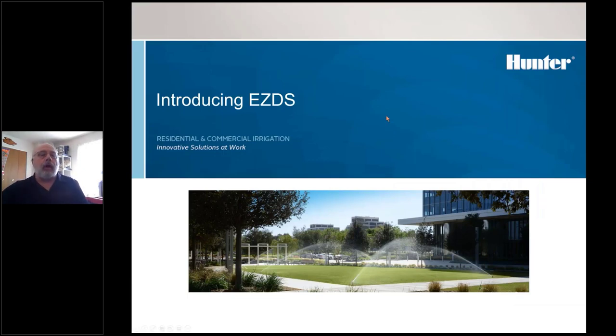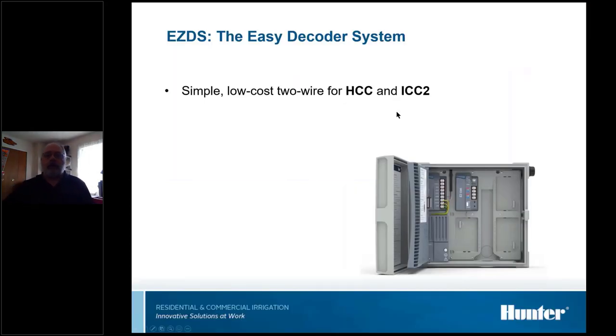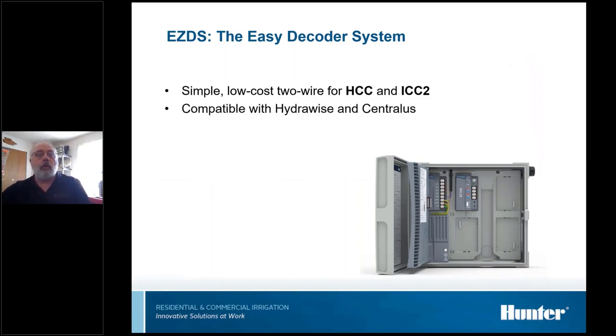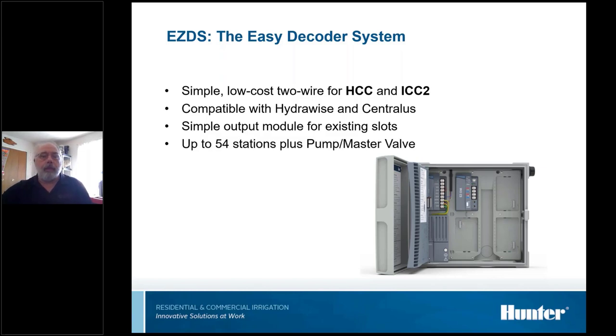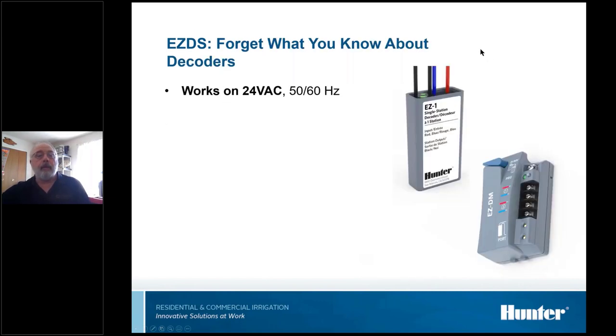So our new two-wire controller is the Easy Decoder System. Basically, Easy is an add-on module. We can use it on either an HCC or an ICC2 controller, which are the HCC with Hydrawise and the ICC2 with the Centralus control platforms. It's just a simple module that you add to existing slots on the controller. It'll bring you up to 54 stations plus a pump master valve.